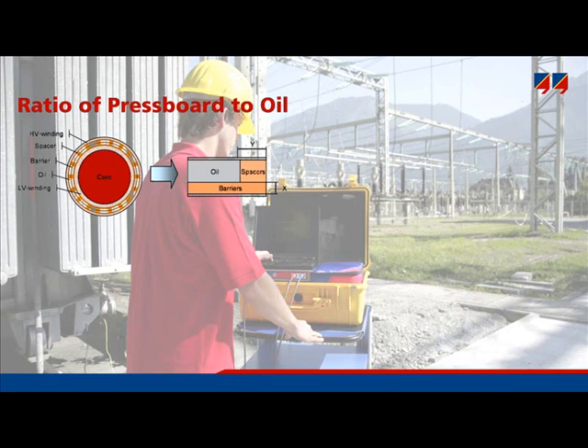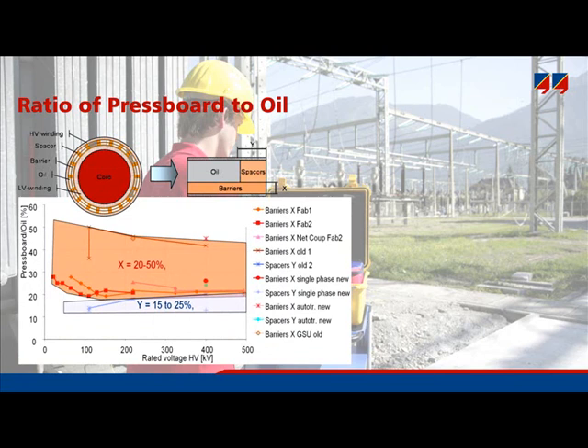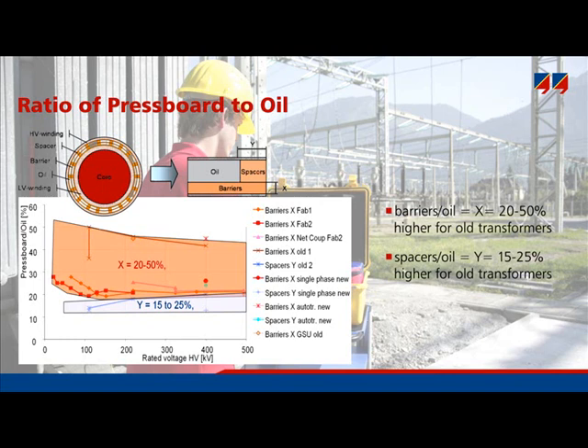The ratio of pressboard to oil is addressed here. The cylindrical transformer insulation is modeled by areas of oil, spacers, and barriers. X represents the volume percentage of barriers and Y that of the spacers. The diagram shows geometry conditions of real transformers: spacers are always between 15 and 25%, while barriers range from 20 to 50%. Old transformers typically have higher values; new transformers have rather less pressboard. These limits are set in the DIRANA software, accessible via the advanced tab settings, and the definite geometry condition is calculated by the software.